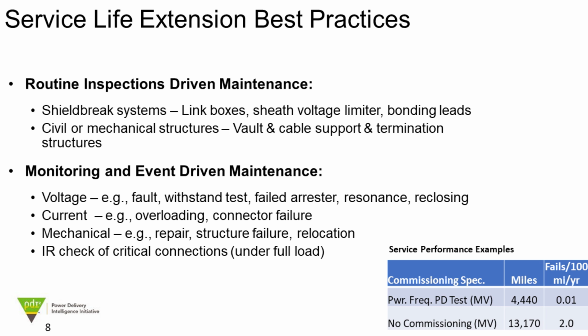But as a setup for the next slide or next point, there's ways of monitoring these assets. But before I suggest that we move on to the next slide or ask for other comments, I want to point out, here's some data here. 4,000 miles of power frequency PD testing, 0.01 failures per 100 miles per year, whereas doing no commissioning test, we've seen ranges anywhere from 1 to 4, even to 6 failures per 100 miles per year. So you're looking at well over an order of magnitude of performance improvement if we've done an effective commissioning test.